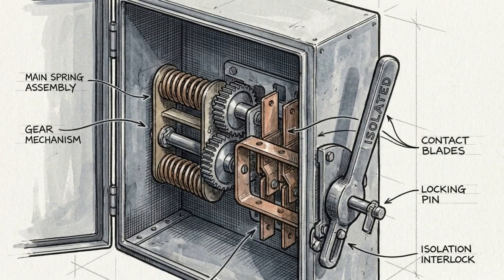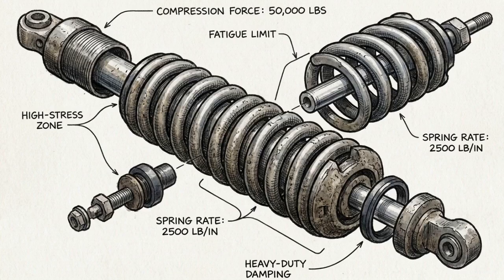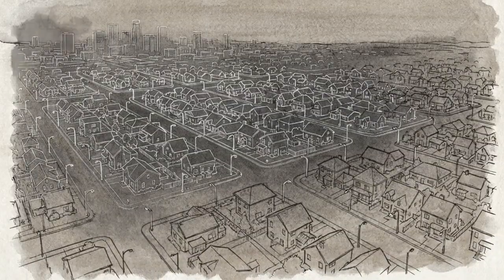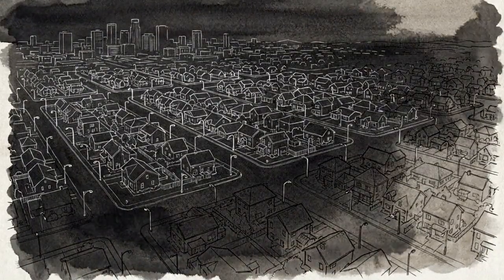Once the microgrid fulfills its mandate to support the larger system, it evaluates the outcome. If the broader grid is still failing, the microgrid will activate its switches and isolate itself. IEEE 1547 transforms these resources into localized shock absorbers. They must endure the trauma to save the network before they are allowed to retreat to safety. The microgrid is now isolated, but the macrogrid is dead. The local system is standing in total darkness.